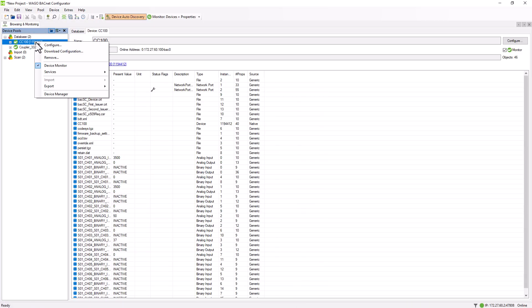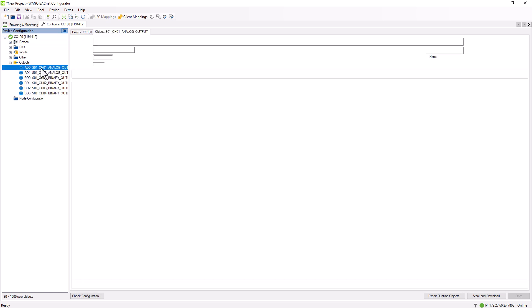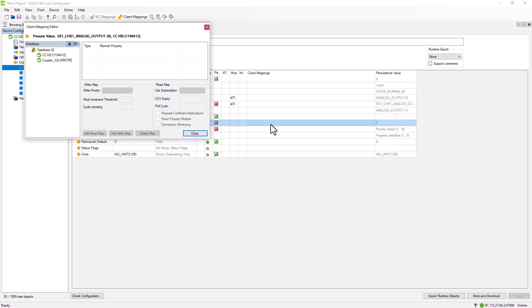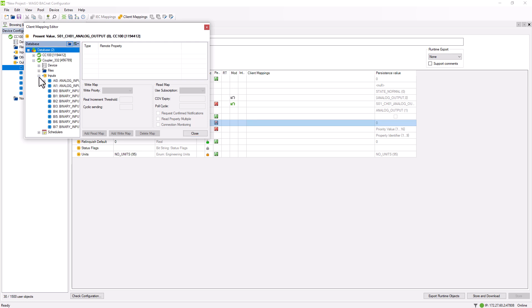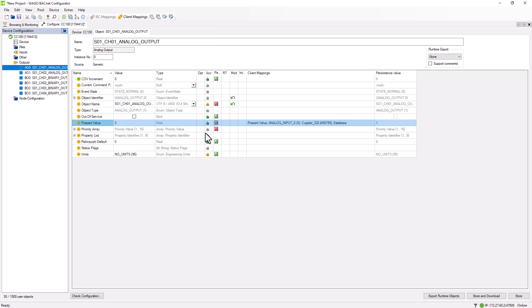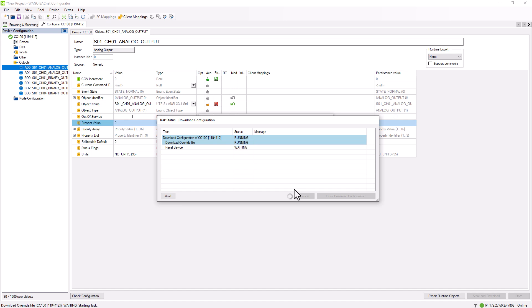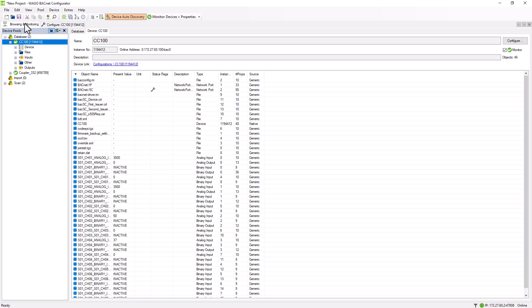The hardware output can also be switched through the coupler input. Just the same, analog values can be subscribed by using the Read function, but a threshold must be defined to determine the magnitude of the value change. Without this threshold, any minor change would send a COV telegram, potentially overloading the fieldbus quickly.